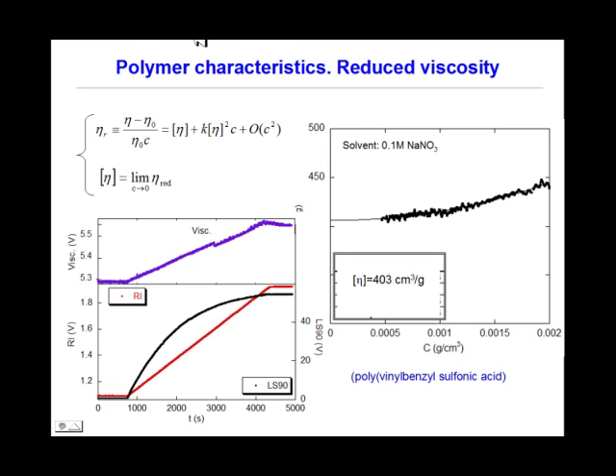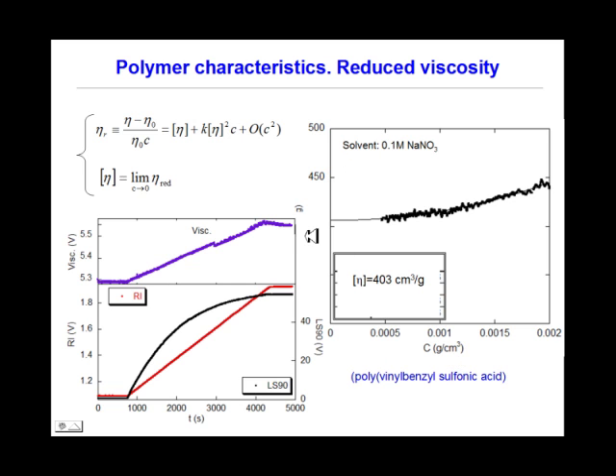Shown here are data from an automatic SEC experiment where polymer concentration was varied. Viscosity increases from the solvent level to the maximum concentration. The refractive index signal increases as polymer concentration increases, and light scattering also increases as more polymer is introduced. On the right is shown reduced viscosity versus concentration, and extrapolation to zero concentration gives the intrinsic viscosity.